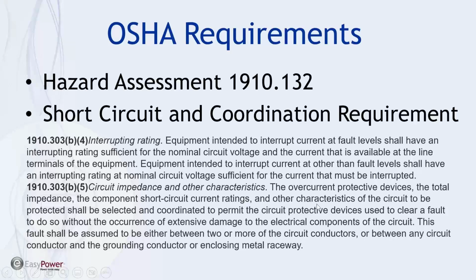So the overcurrent protective devices, the total impedance, the component short circuit current ratings, and other characteristics of the circuit to be protected shall be selected and coordinated to permit the circuit protective device used to clear a fault without occurrence of extensive damage to the electrical components of the equipment. So that's why it's got to be rated for the fault current, because otherwise it's going to blow up like the panel I showed you. It's going to be overdutied. It's not going to be able to handle that level of fault current, and it's going to blow up.